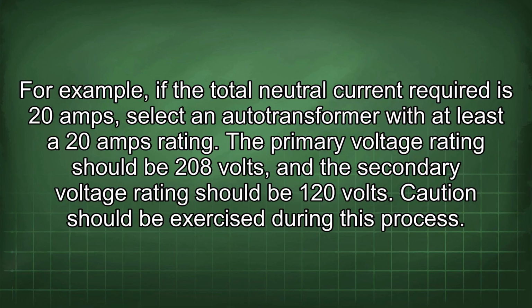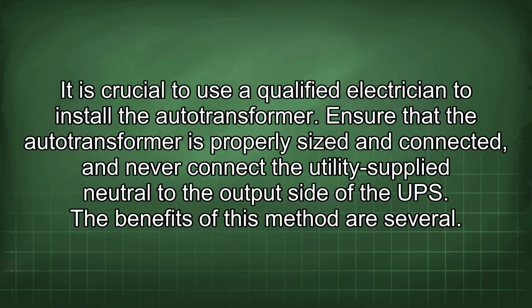Caution should be exercised during this process. It is crucial to use a qualified electrician to install the autotransformer. Ensure that the autotransformer is properly sized and connected, and never connect the utility supplied neutral to the output side of the UPS. The benefits of this method are several.